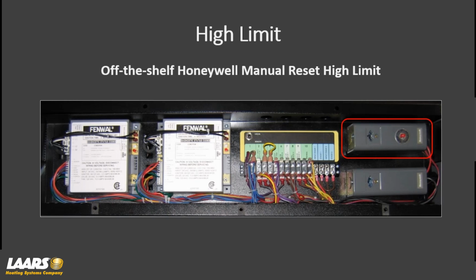Keep them maxed out. Example, if I've got a volume water heating application and I'm trying to maintain 140 out to a system, okay? And returning back, or 145 and returning back at 125. Why would I ever set my high limit at 140 or 150 or 160? Crank it up. Let it do its job. It's there for runaway, for example. Something gets stuck open, it's just a safety. So don't turn these down, because you will start to have nuisance trips, high limit trips.